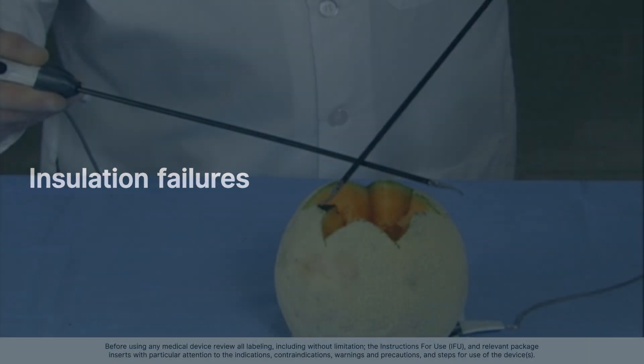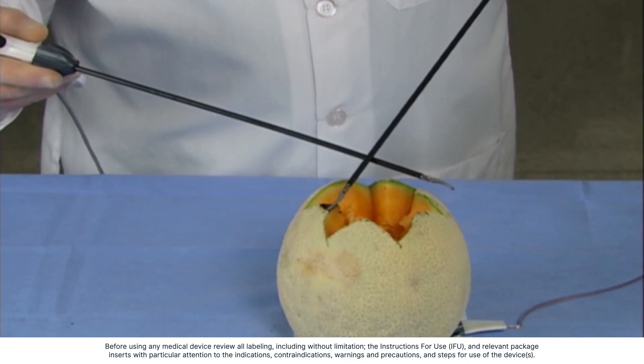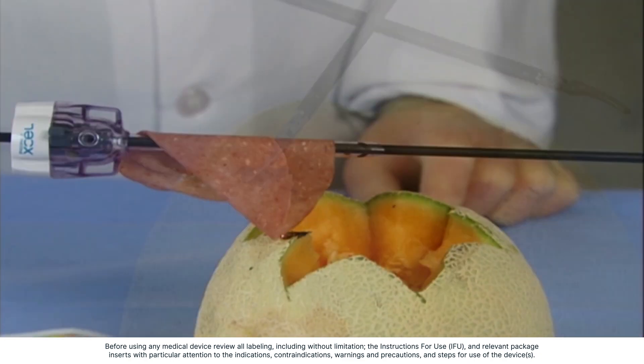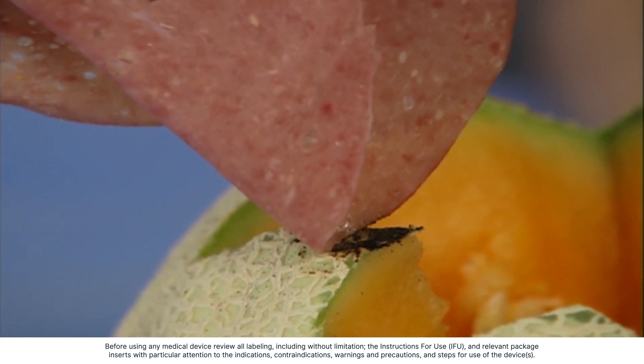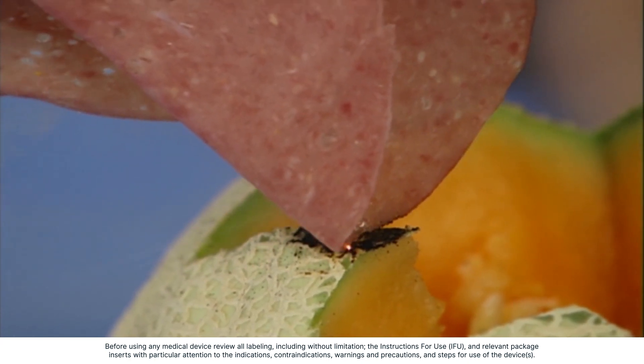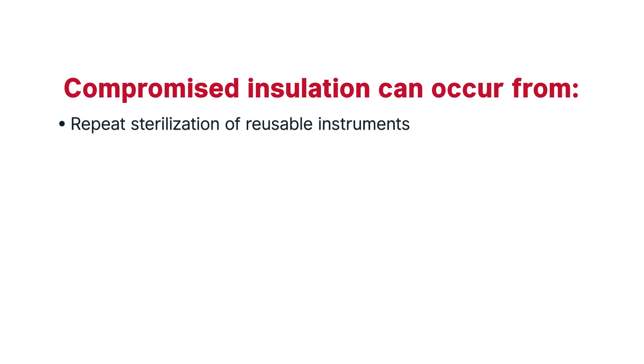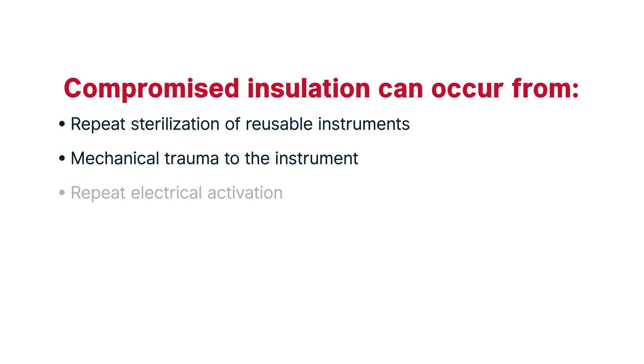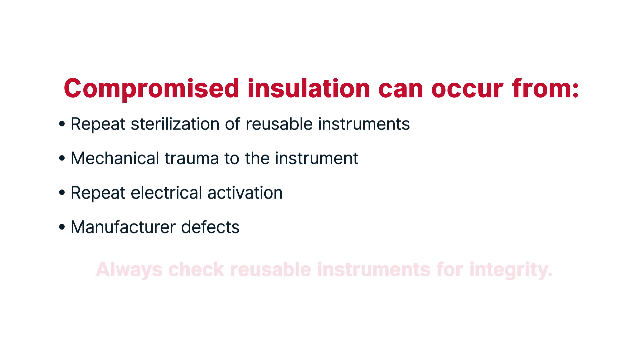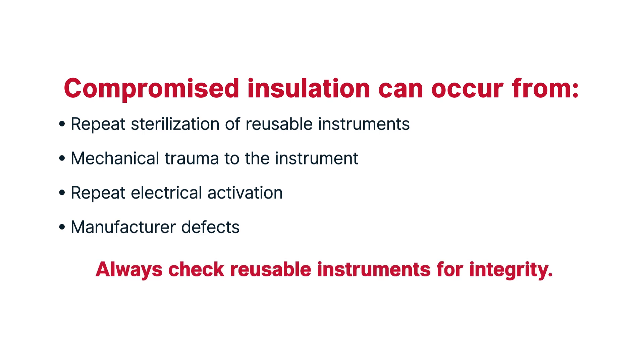Insulation failures. Insulation failures occur when an active electrode's protective coating is compromised. These occurrences can create an alternate route for electricity to flow. If the current is concentrated, it can cause significant injury. As noted earlier, smaller areas of contact have a greater likelihood of injury due to current concentration. Due to the worry of small holes going unnoticed, insulation failure on reusable instruments is a concern. Compromised insulation can occur from: repeat sterilization of reusable instruments, mechanical trauma to the instrument, repeat electrical activation, or manufacturer defects. Before performing monopolar electrosurgery, always check reusable instruments for integrity.